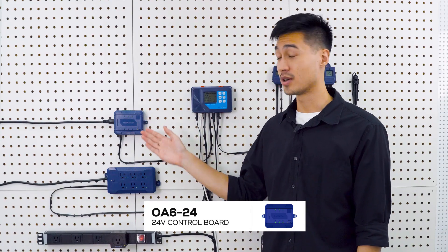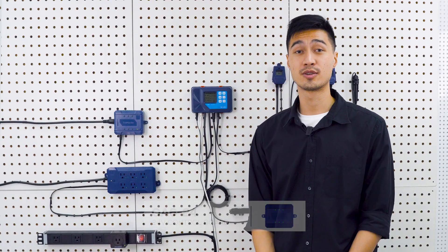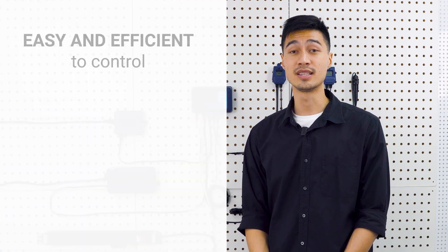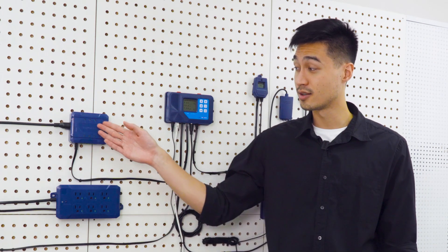The OA6-24 control board is designed to control multiple 24 volt AC solenoid valves and provides an easy and efficient method to control up to six solenoid valves, each with individual timer settings. Do note that the solenoids must have a holding current below 0.2 amps.